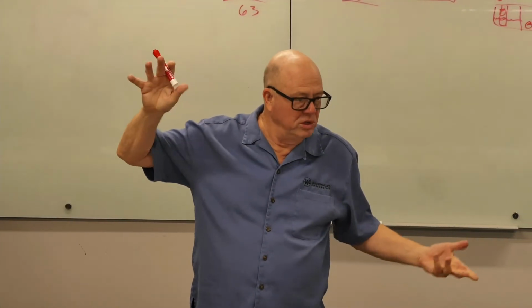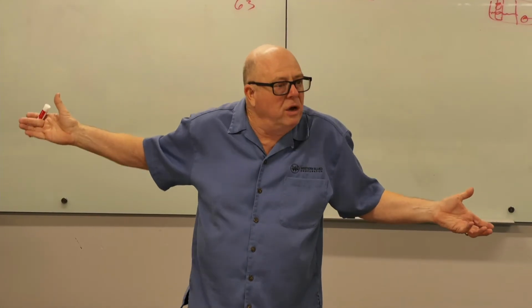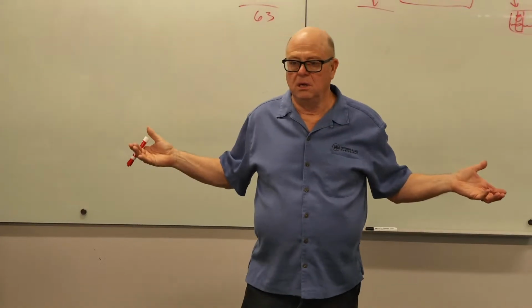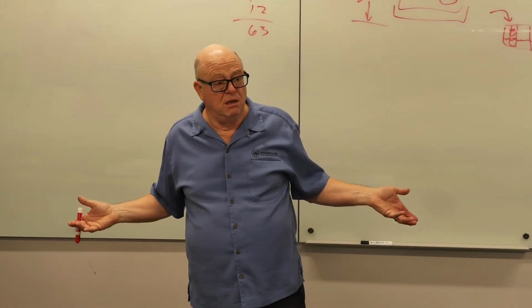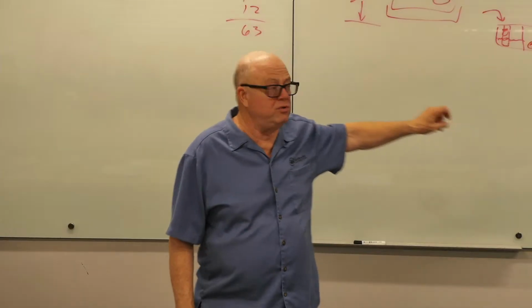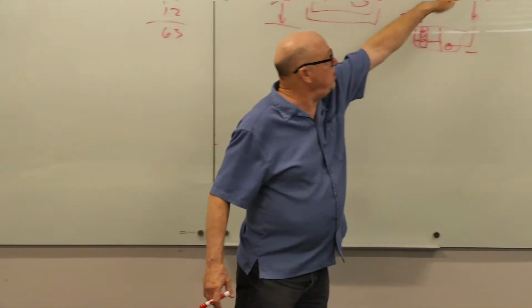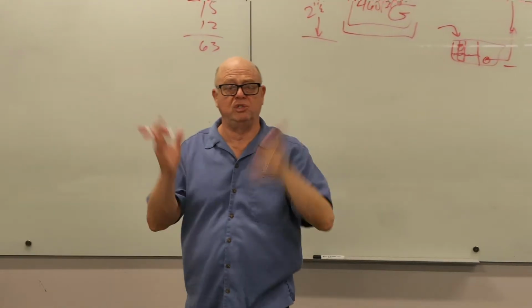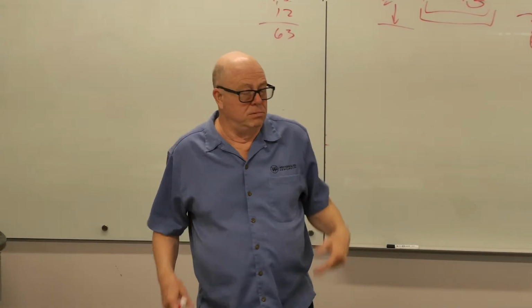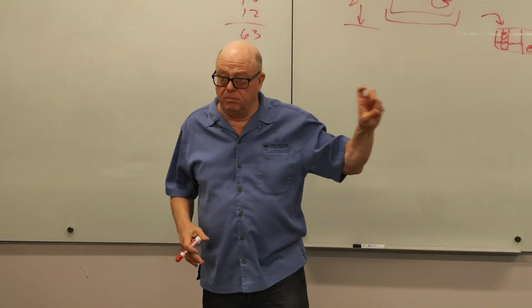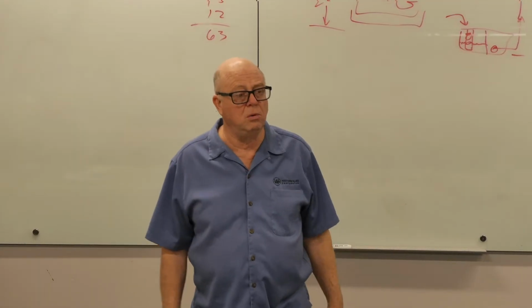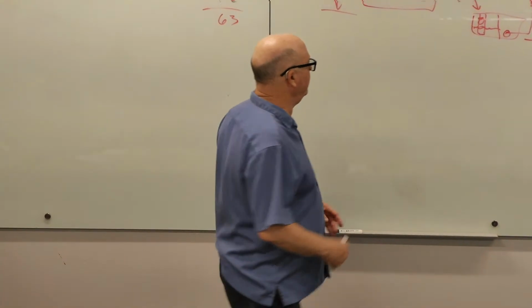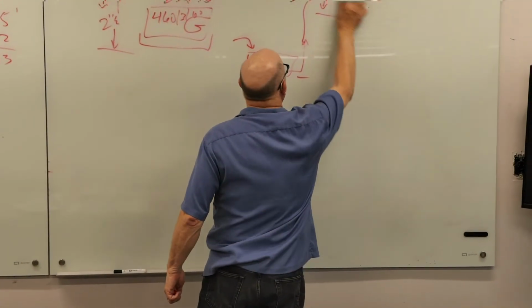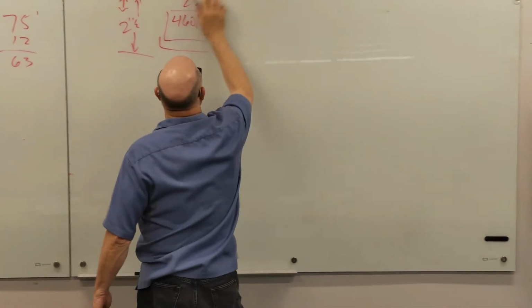And the voltage question comes back to, well, how am I going to power this thing? And how much power does it take? And do I think I've got enough left in the control power transformer? For 2 feet, a 24 volt condensate pump will work just fine. Do I have the VA to drive it? I would hope so, but do I? That's another area where you don't want to put in 40 of those and then suddenly find out it won't work.